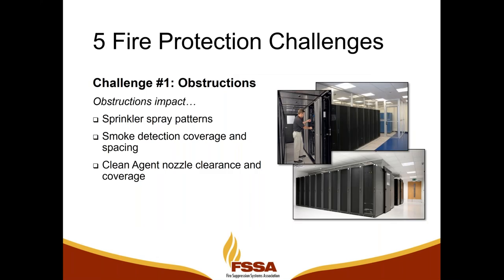So there's five fire protection challenges, and let's start with obstructions. Here's the way I look at it. The containment system is really building a partition to separate the hot air from the cold air, whether it's hot aisle containment or cold aisle containment. There's a new partition in the space. That partition is an obstruction to our fire protection systems and their performance. So those obstructions can impact the sprinkler spray patterns in the space, can impact the smoke detection coverage and spacing, and they can also impact the clean agent system nozzle clearances and the coverages of those nozzles. So we need to be aware that that's a challenge.